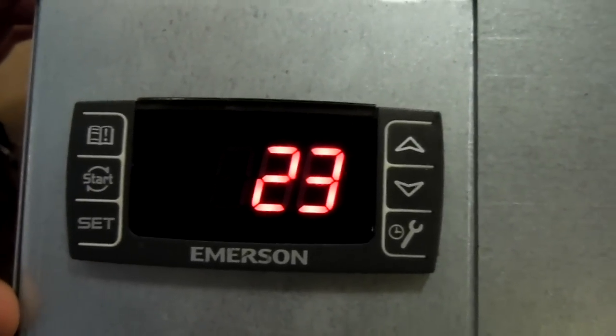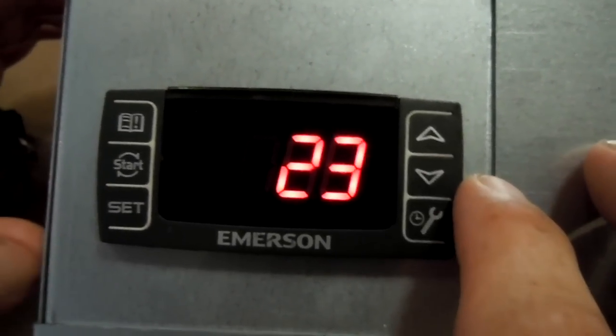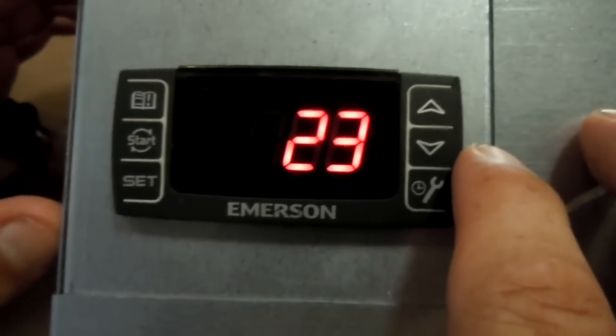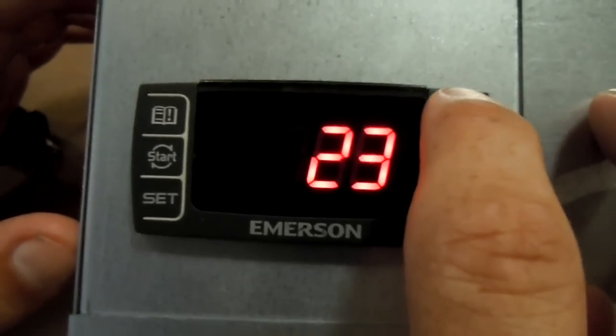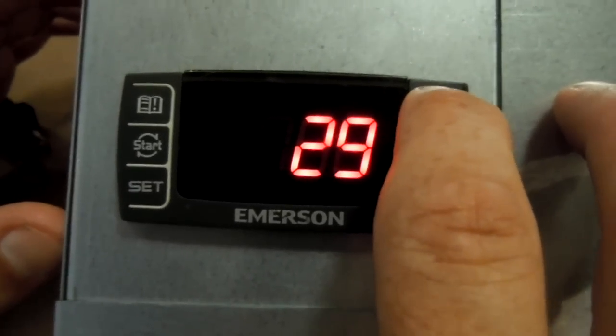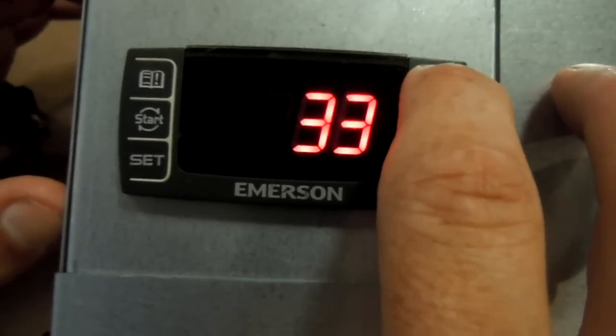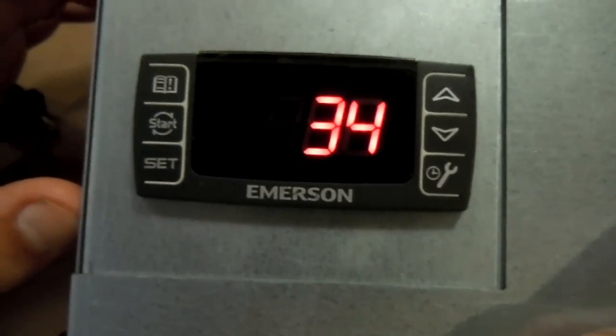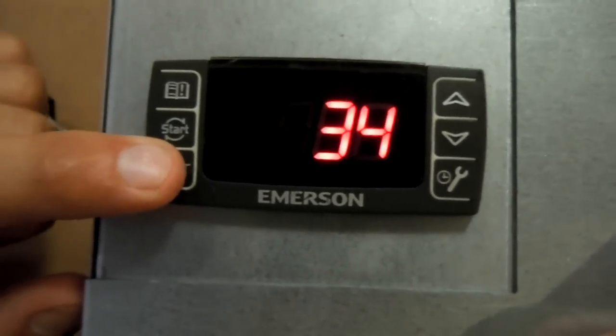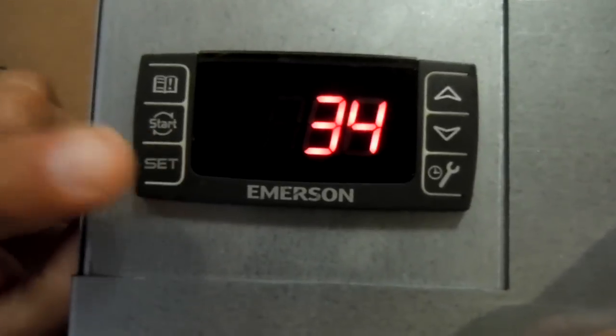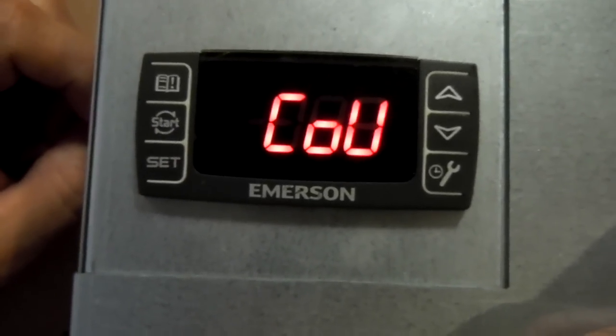And right now your cut in for low pressure is set at 23. So what we're going to do is we're going to bump that up a little bit to about 34. And then to lock that in, you press set and set again, and that's locked in.